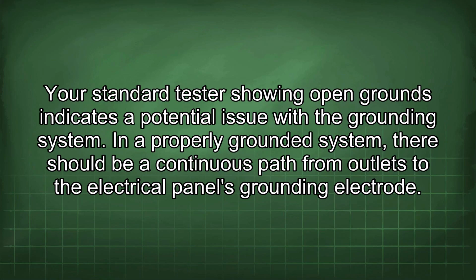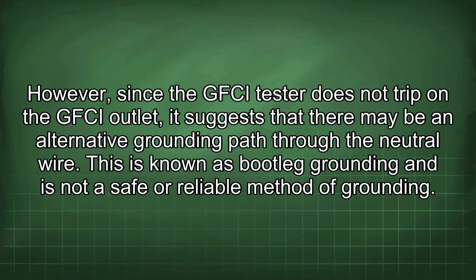Your standard tester showing open grounds indicates a potential issue with the grounding system. In a properly grounded system, there should be a continuous path from outlets to the electrical panel's grounding electrode. However, since the GFCI tester does not trip on the GFCI outlet, it suggests that there may be an alternative grounding path through the neutral wire. This is known as bootleg grounding and is not a safe or reliable method of grounding.